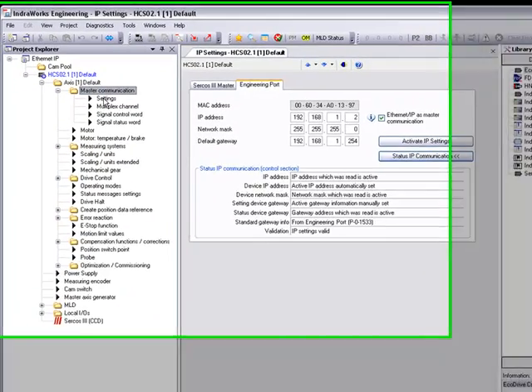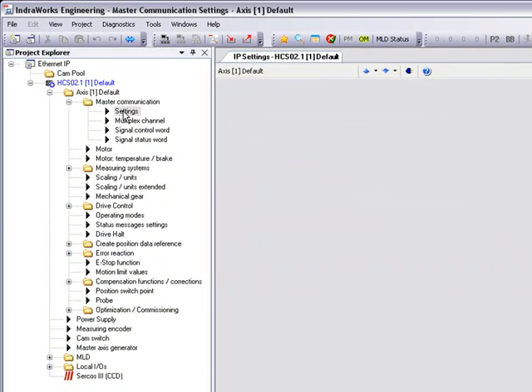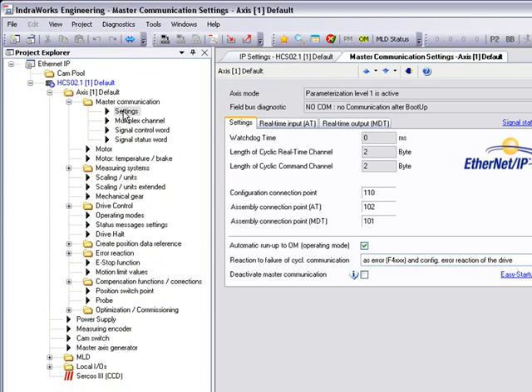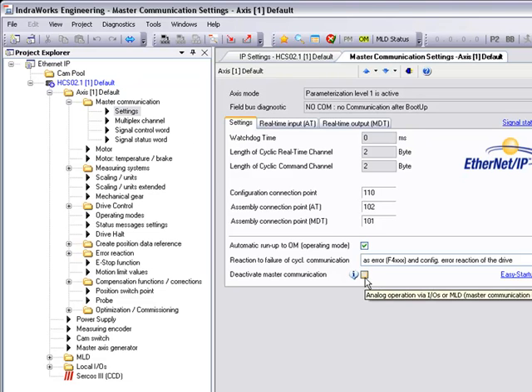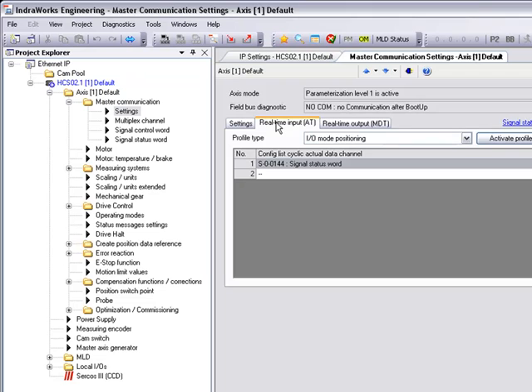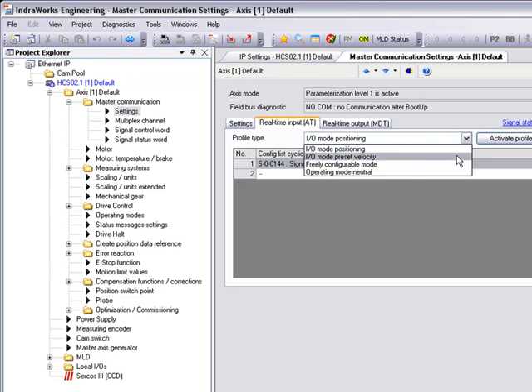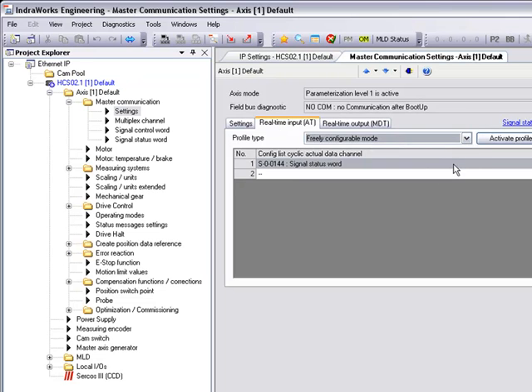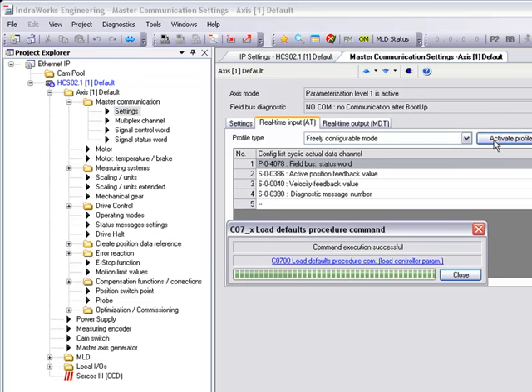Once our TCP IP settings are verified, we'll go under our master communication settings and we'll make sure that our deactivate master communication box is not checked. From here, we'll set up our profile type to be our freely configurable mode and we'll activate that profile.